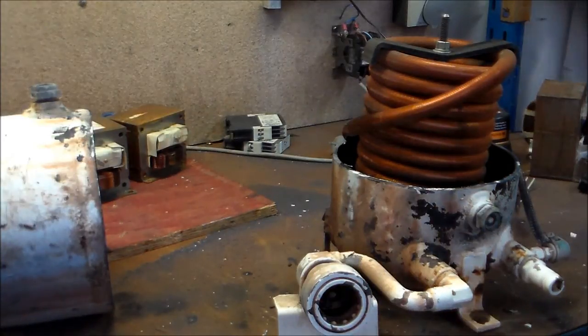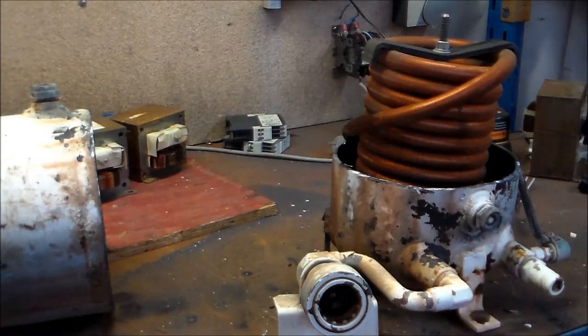I really thought this was a receiver dryer, but it could be a receiver, but there's no drying element. Well, there's no desiccant in there as such. Maybe this is an oil sack. Yeah, I have a feeling this is just a water condenser, fellas.